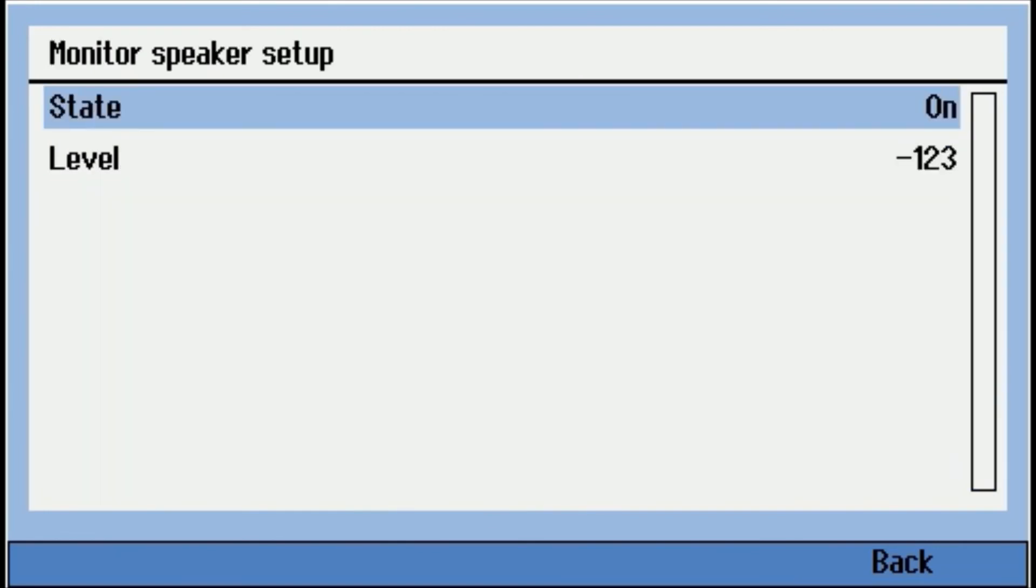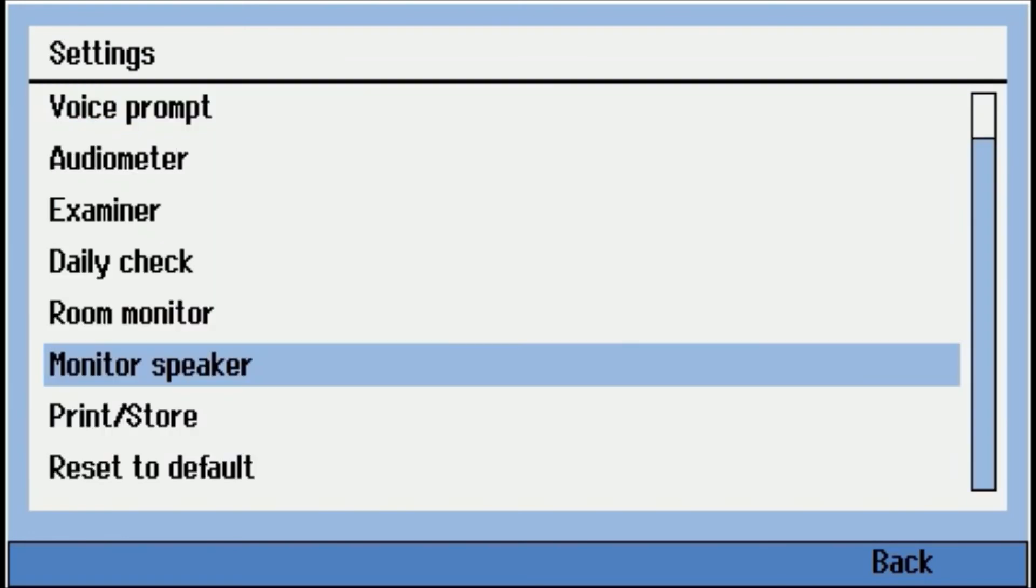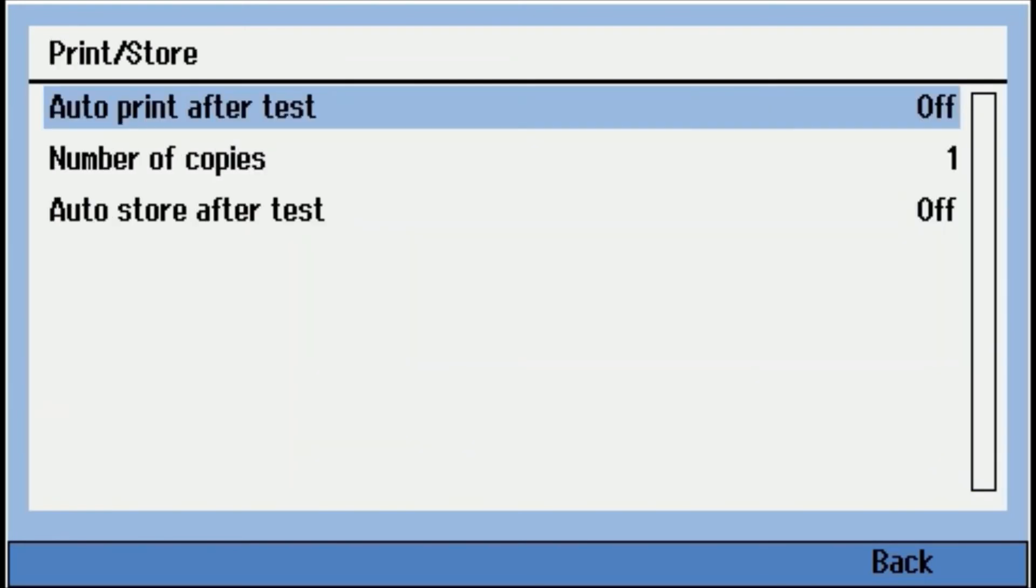Monitor speaker. So there's an internal microphone. So you'll be able to talk to the person in the booth. It's pretty much just an on-off. Print/store. So this will let you automatically print a test result or store it internally to the database or kind of a mixture of the two. The RA 360 will hold 500 records internally.